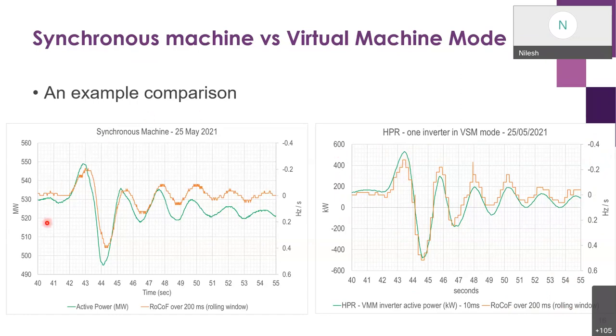And you can see the maximum or the higher output when the rate of change of frequency is higher. On the left-hand side, you could see a similar response, not exactly the same, from a synchronous machine. When the rate of change of frequency is higher, you get maximum megawatt coming out from the battery. After a few seconds, the governor response kicks in, and that's why you don't see it exactly matching.